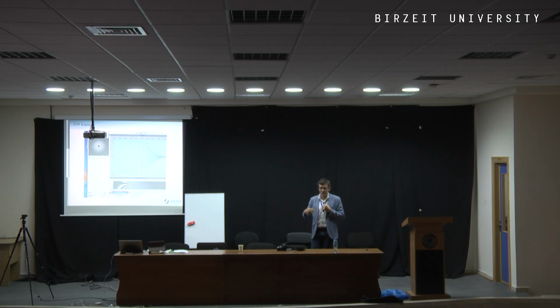What we record are not direct projections, they are interference phenomena which depend on a huge number of parameters. And when we do calculations, normally you have 30 or 40 parameters that have to be included which describe the sample, the electron microscope column, and the imaging conditions, and those parameters often need to be varied iteratively until you obtain a best match with simulations to understand experimental observations.